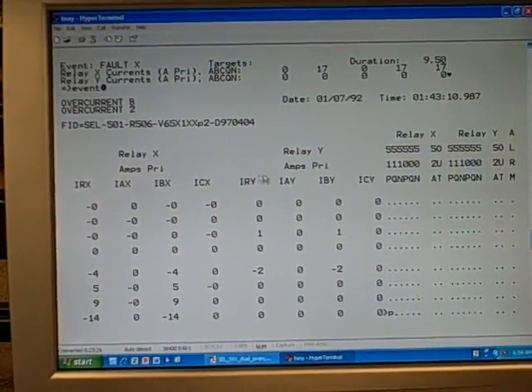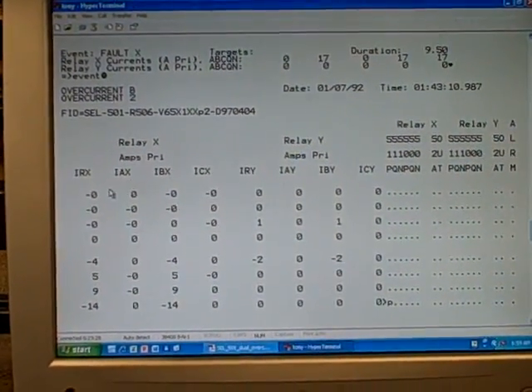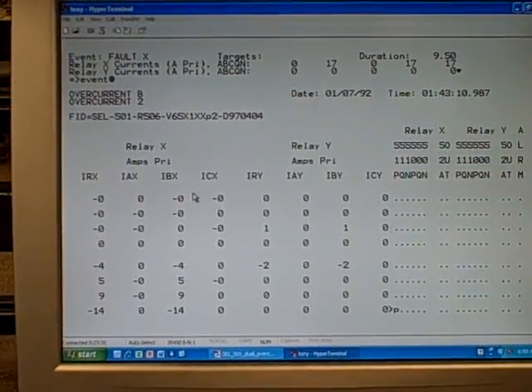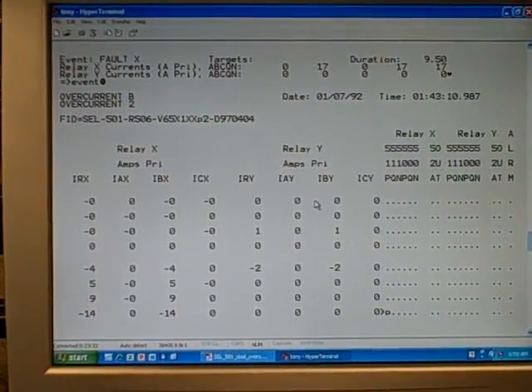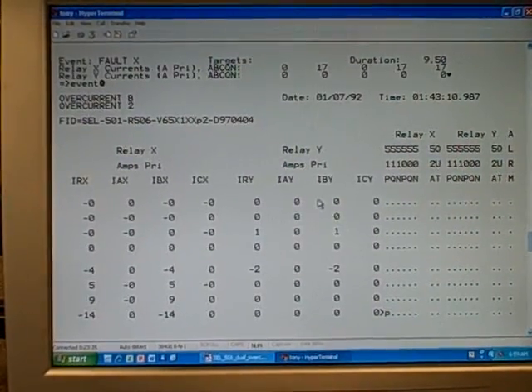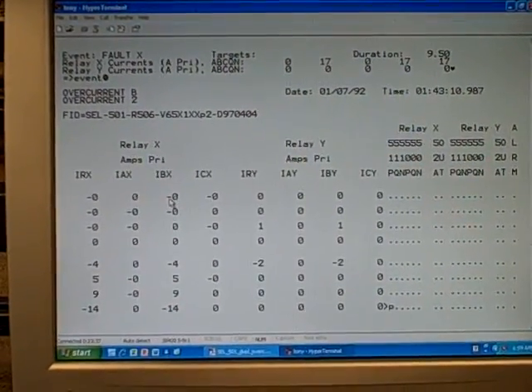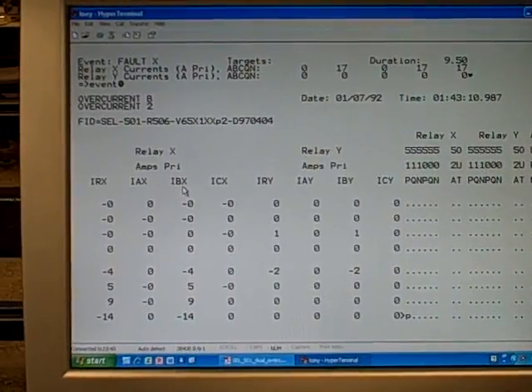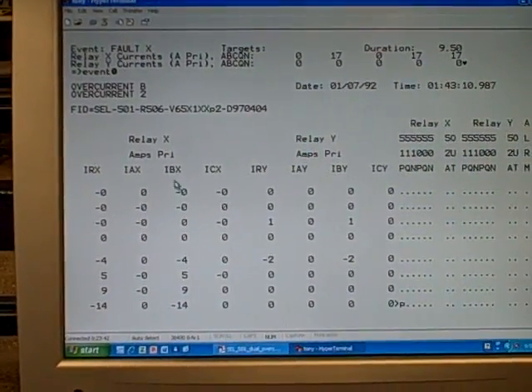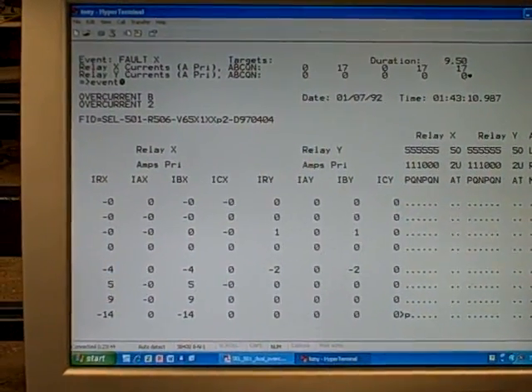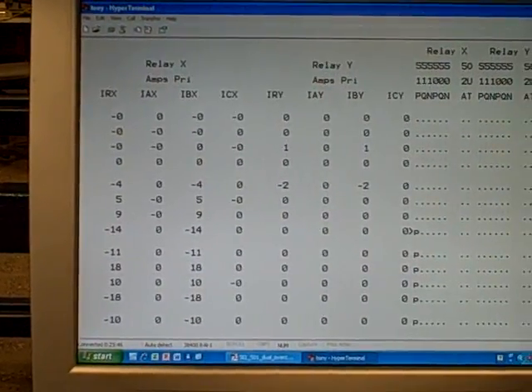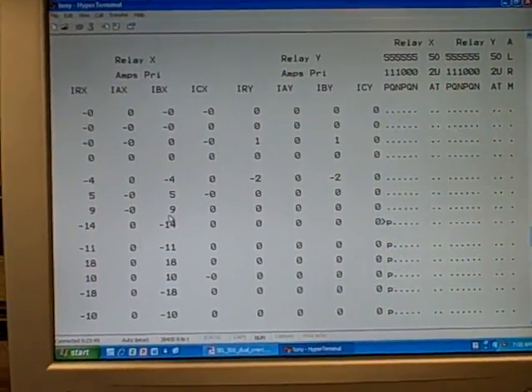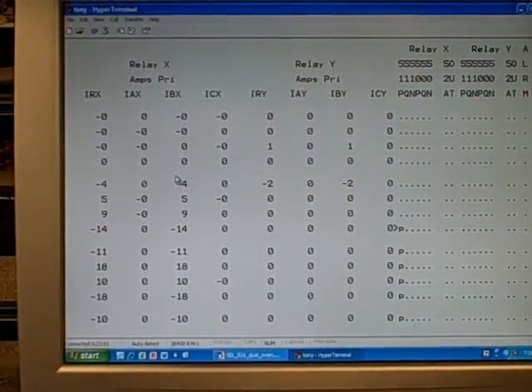We see relay X, relay Y. We see the various currents for A, B, and C phase for X, and A, B, and C phase for Y. We're not using relay Y, we're only using relay X right now. In particular, we're only using phase B of relay X. So if you look at the column for IBX, that is the only column for which we see any numbers of the three different phases. We're using it essentially as a single phase relay.